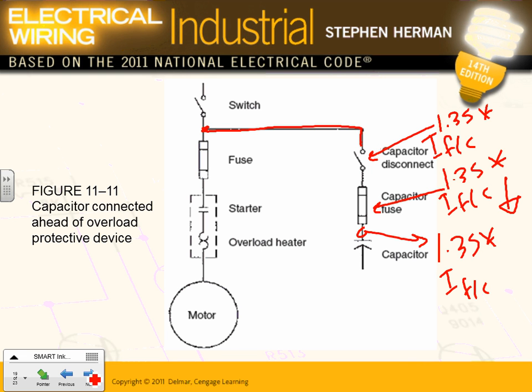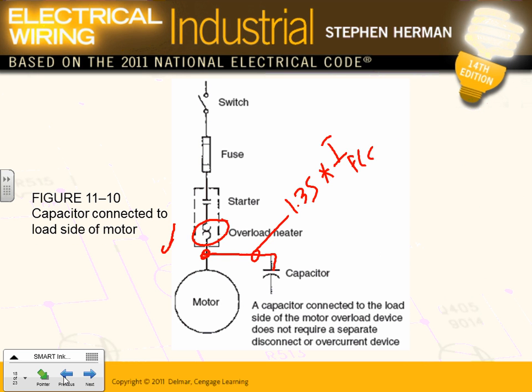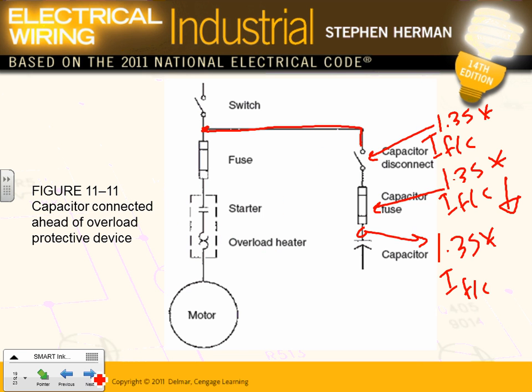And that will be to correct the power factor right at the level of a motor. Any comments, guys? Any questions about this? Two ways. One way is to put it right here on the load side of a disconnect, the load side of a disconnect starter overload protection device. The second way is to connect them on the switch. Which way is the better way?